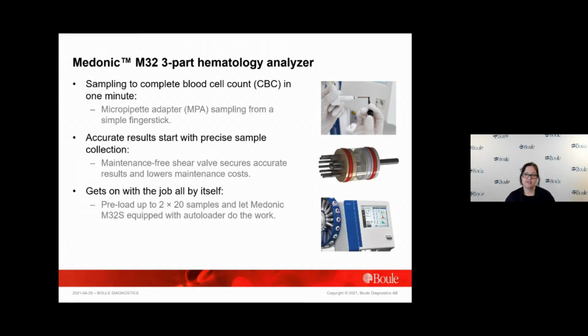Medonic M32 provides the following: reporting of a complete blood count from a low sample volume enabled by the MPA module that supports capillary sample analysis directly from a fingerstick. Measurement accuracy enabled by the shear valve, which has a closed design to minimize the risk of dust particles entering or salt buildup that might cause leakage. And walk-away automation that liberates time for other tasks in the lab, enabled by the automation wheels with a design that provides constant mixing of queued samples, which is especially important for samples with a high erythrocyte sedimentation rate.